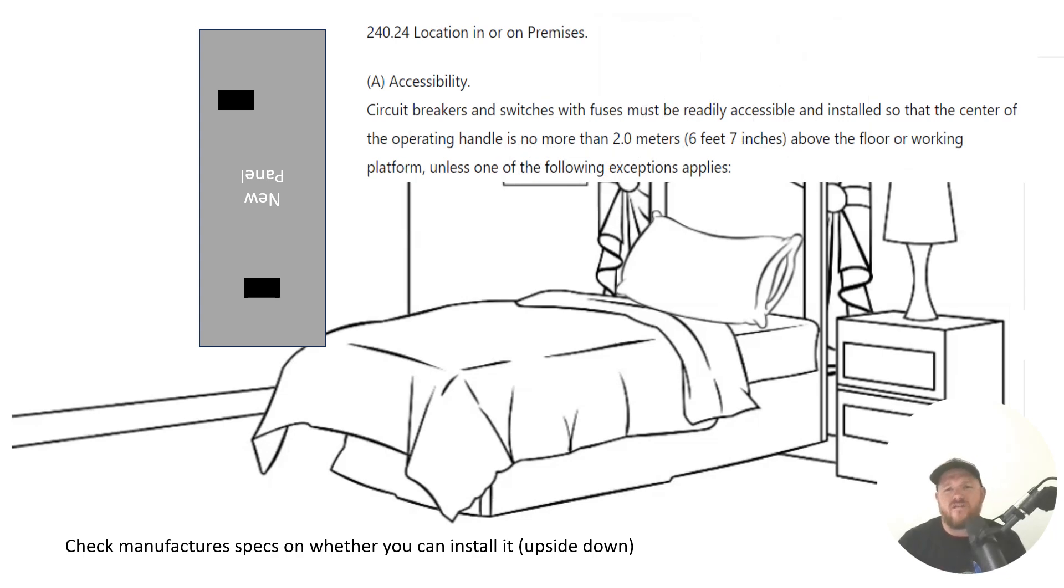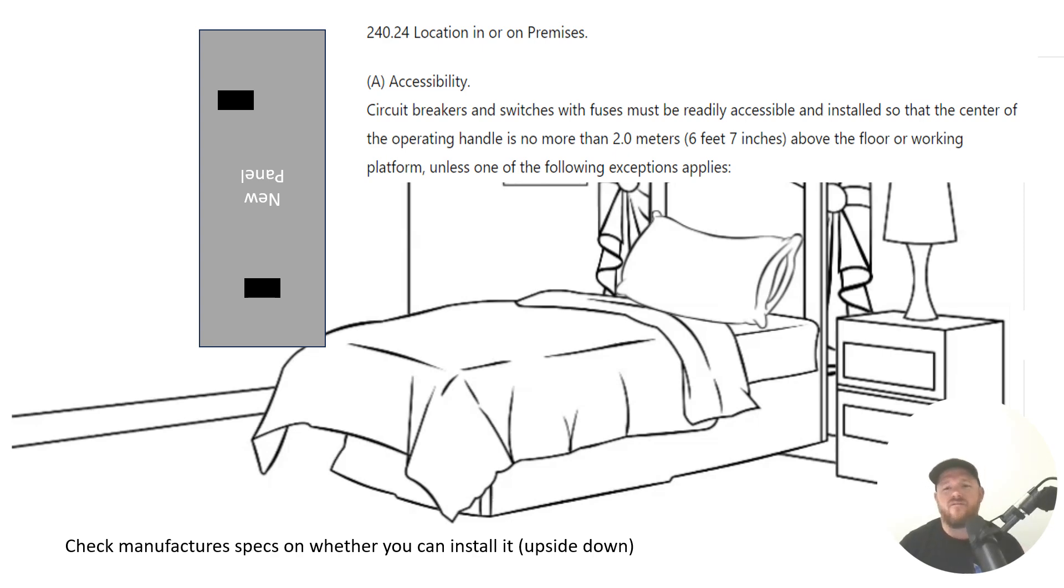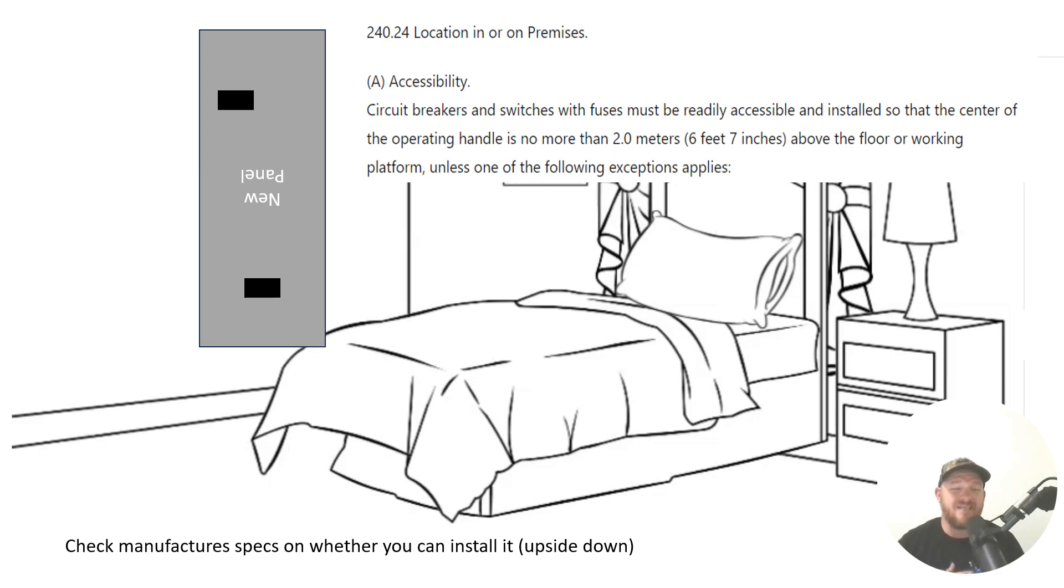Let's look at the paraphrase code language. It says circuit breakers and switches with fuses must be readily accessible and installed so that the center of the operating handle is no more than six foot seven inches above the floor or working platform unless one of the following exceptions apply.